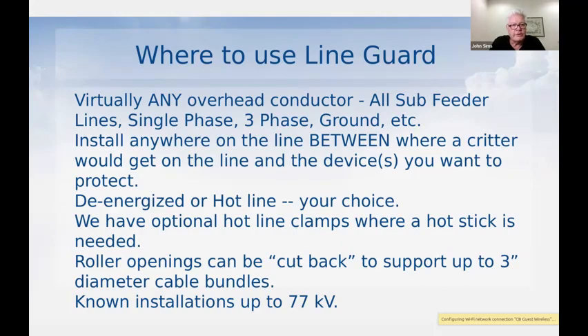And so we just basically say, install it anywhere between where the critter would get on the line and the device you want to protect. In the case of a sub, it would be outside the vertical line that the fence around the sub creates, so that if they get knocked off the line guard system, they're dropping outside the fence, not inside the fence.